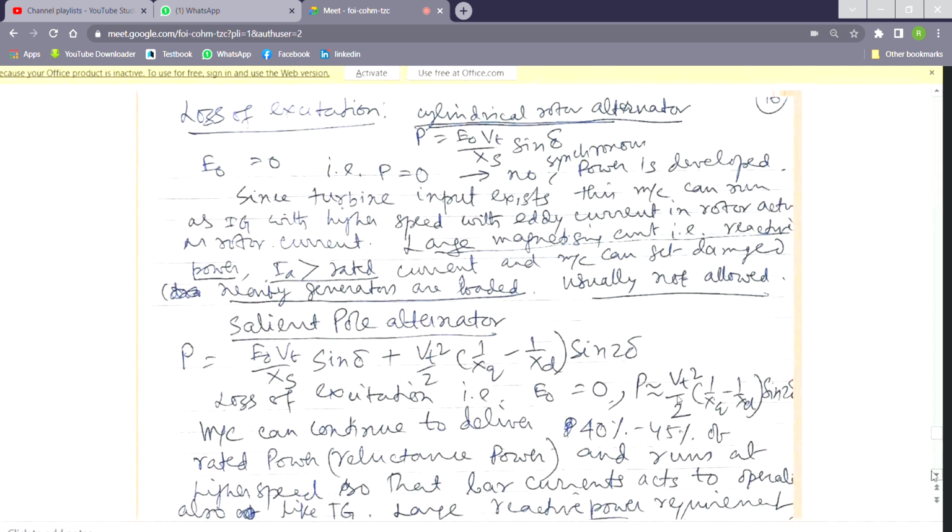But due to certain faults, maybe a relay has tripped, some overcurrent has gone, or something has been missed, the field current is lost. I mean, the field current suddenly becomes zero. Now, when the field current is zero, the power is given by E V by X sin delta, and E depends on the field current. Barring residual magnetism, there is no naturally generated EMF, so E is zero and the power equals zero. So no synchronous power can be generated.